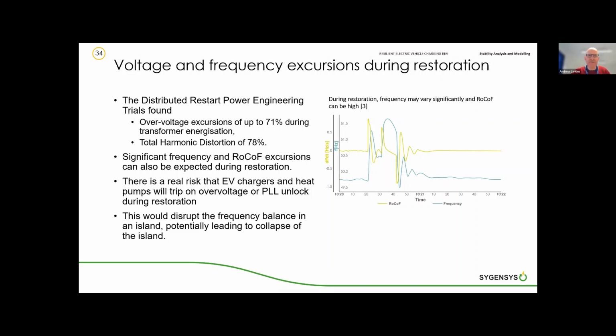So significant frequency and rate-of-change-of-frequency excursions can also be expected. And this graph on the right is taken from the simulated results of a smart zone controller looking at distributed restart. And again, you can see very large frequency and rate-of-change-of-frequency excursions. So there's a real risk that EV chargers and heat pumps will trip on overvoltage or unlock phase lock loops during restoration because of these highly disturbed conditions. And tripping of large tranches of load disrupts the frequency balance in an island and potentially cause that island to collapse. So this is an area which I think is a potentially significant concern in the future, is how these load islands will behave during restoration.